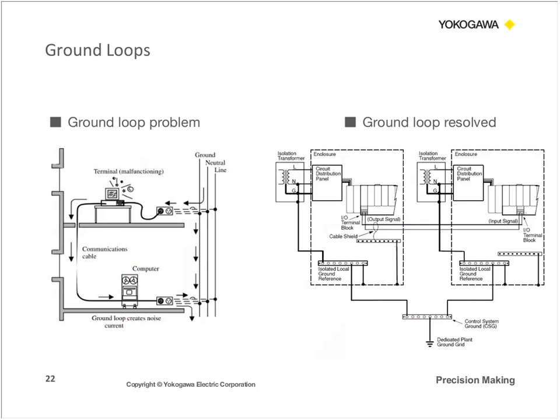So let's take a look at ground loops. Let's illustrate the problem so we can really understand how these situations can occur. To illustrate the concept, take, for example, the picture on the left where we have the terminal station in one room. This terminal station could be a test cell, for example. It could be a motor. It could be a switch mode power supply. Basically, it could be any sort of test system that you have. And in the other room, you have a computer or a test stand. And what happens is if you connect the two stations to the power receptacle and you run a communications cable between the two, you've now created a ground loop.